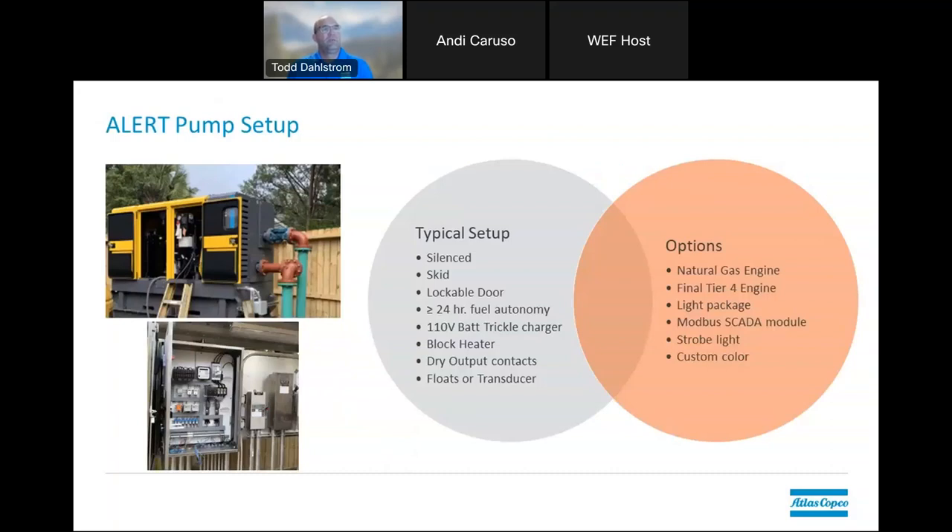Here are pictures of a typical system — you have your traditional submersible pump down in the wet well of a lift station, and here is the sound-attenuated enclosed unit on a skid. The permanent piping is down in the lift station. Lockable doors are typical, and you want to have 24-hour fuel autonomy. Trickle chargers and block heaters are very common. Options include floats and transducers, natural gas engines, Tier 4 Final, remote Modbus SCADA systems that tie into the municipality's current system — so you can see where all lift stations are throughout the city — as well as strobe lights and custom colors.